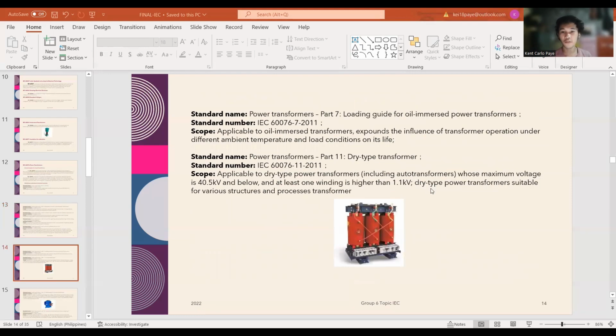And next is the loading guide for oil immersed power transformers. So this parameter standard is applicable to oil immersed transformers, and expounds the influence of transformer operation under different ambient temperature and load conditions on its life. It also provides guidance for the specifications and loading of power transformers from the point of view of operational temperature and thermal aging. So it provides recommendations for loading above the nameplate rating and guidance for the planner to choose appropriate rated quantities and loading conditions for new installations.